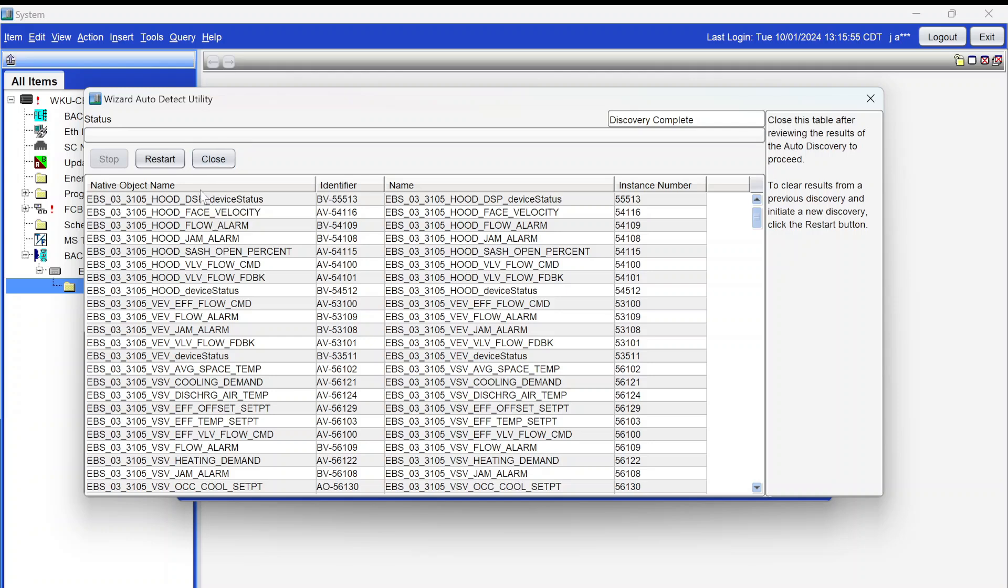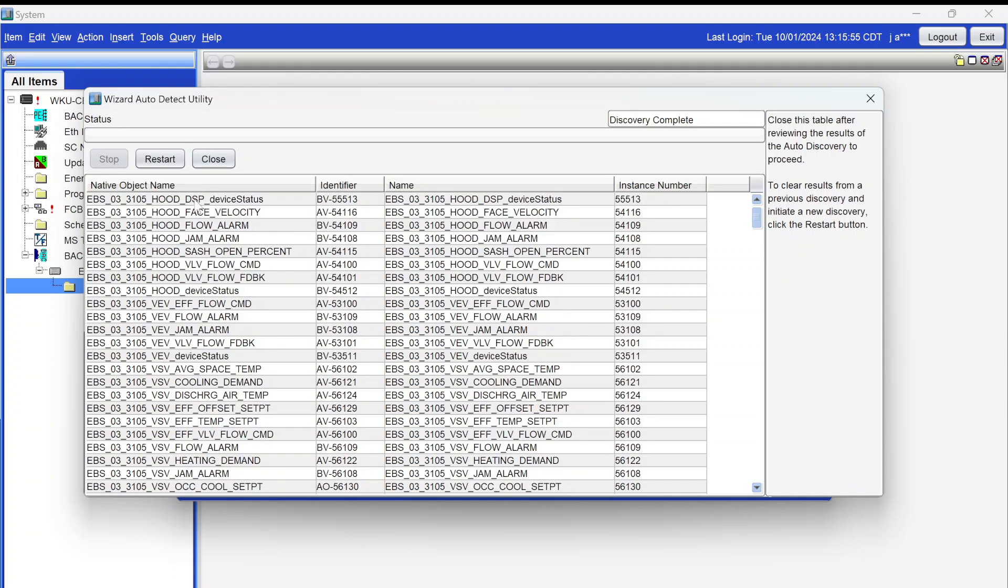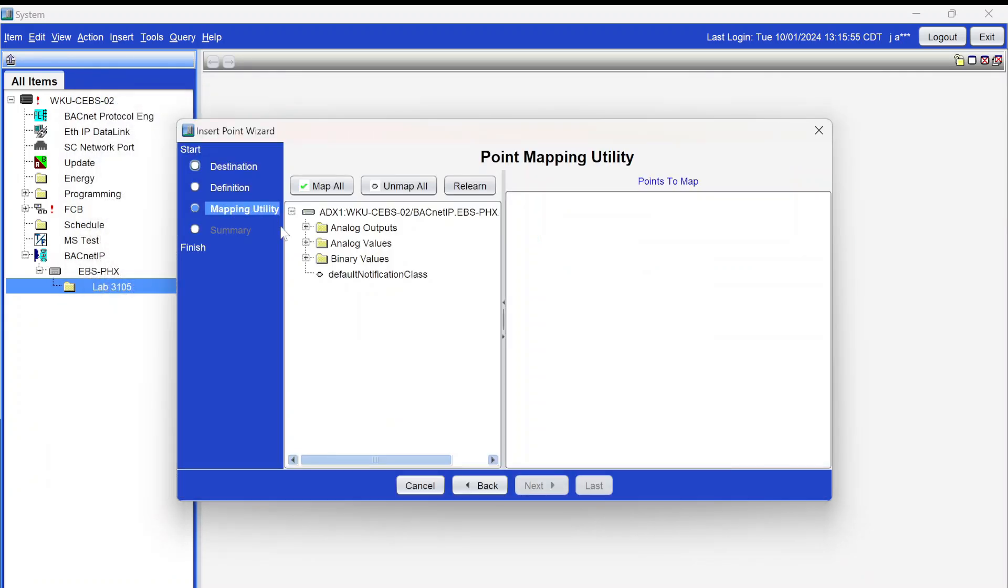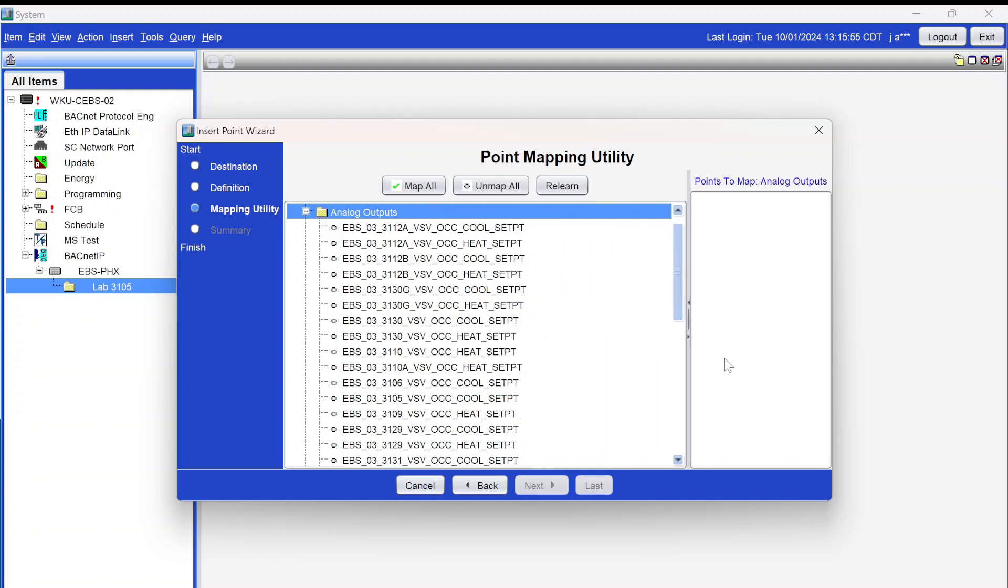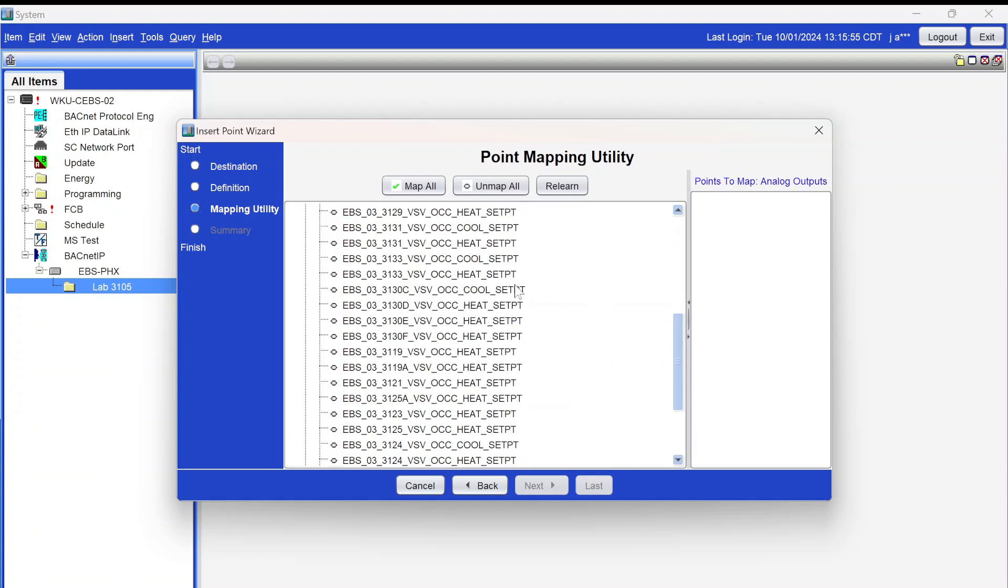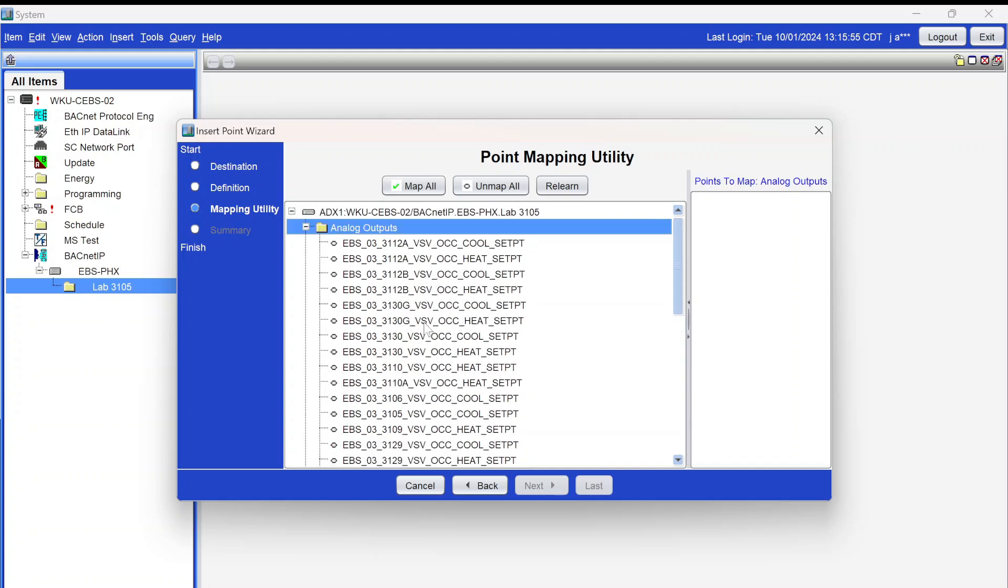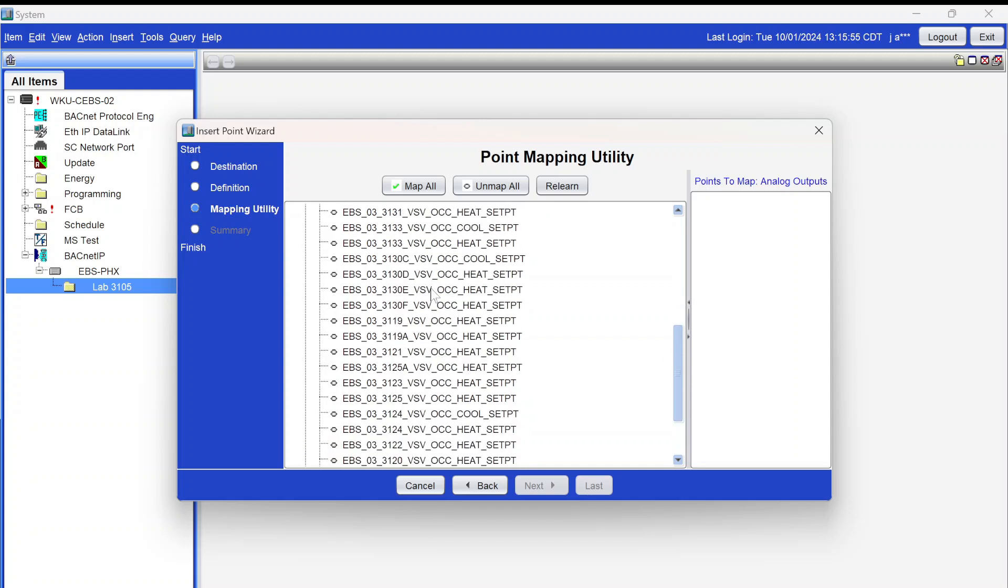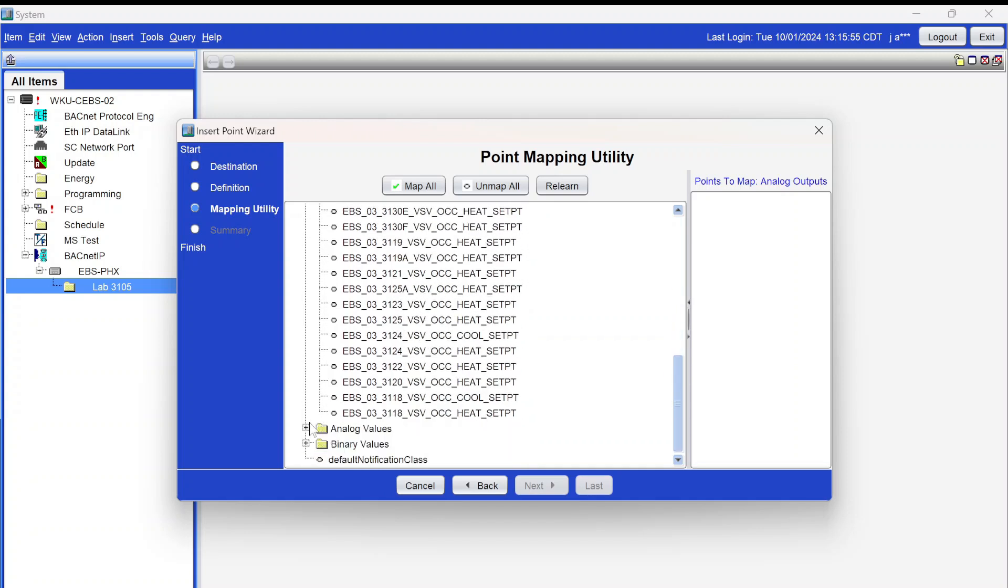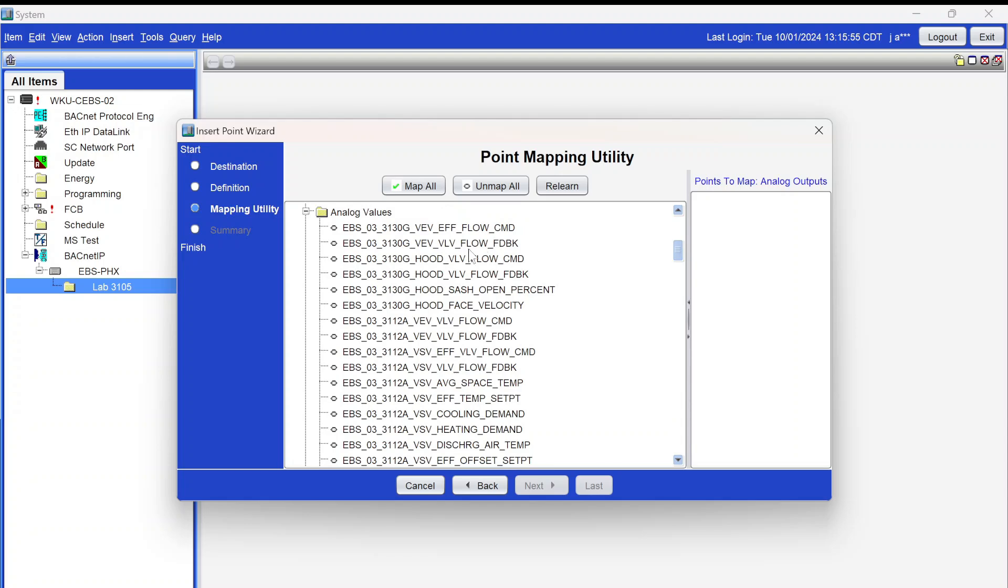You can see the points list here, and it's just everything that's in that Jace. But as I mentioned, you can use subfolders and things like that. I could put the hoods in that room underneath one folder and so on. But basically what I'm going to do is I'm just going to take a room at a time and pull everything for a particular room into this folder, one of these folders. And again, I'm showing you this in SMP, and then momentarily we're going to look at how it looks in MUI. I think MUI actually has a little bit better features, and I'll show you why when we get there. You can see here I'm going through each of these folders and anything, any of these points that are related to that particular room number. Basically what I've got to do is filter through all of these folders, and then I've got to double-click each of the points that are related to that room number.